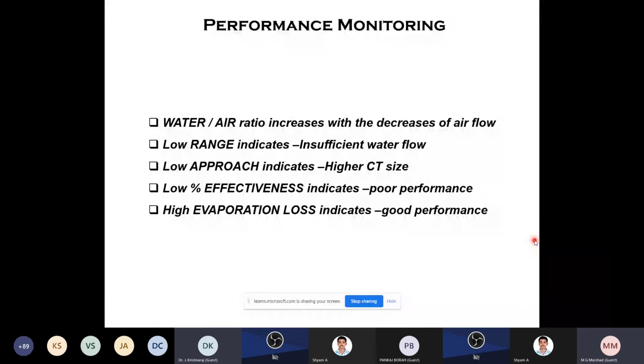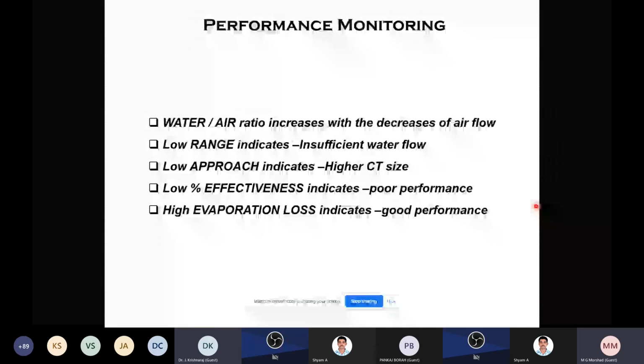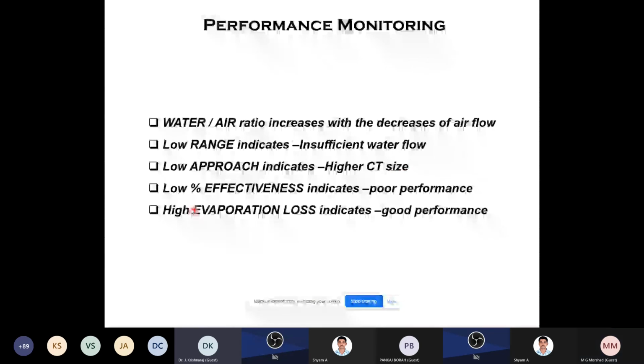Suppose the air-water ratio increases with a decrease of the airflow. Low range indicates insufficient water flow. Low approach indicates higher cooling tower size. Low effectiveness indicates poor performance. Higher evaporation loss indicates good performance. So if evaporation is more, the performance is very good. Low effectiveness means poor performance. So these are all the key observations related to the cooling tower. Okay.